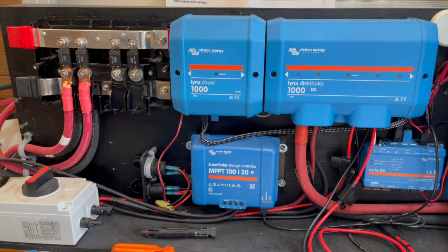You have to consider the total capacity of your server rack. It's probably around 400 to 600 amps. You have to consider the capacity of your inverter. Just how many watts are you going to be providing at any given time? What's the amperage you're giving? I would say in most cases, people who are using server racks probably need a 4/0 gauge wire coming from the server rack to their system. And it should be the same length for the positive and for the negative.